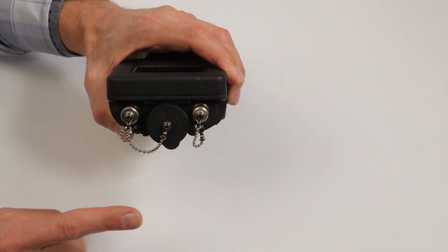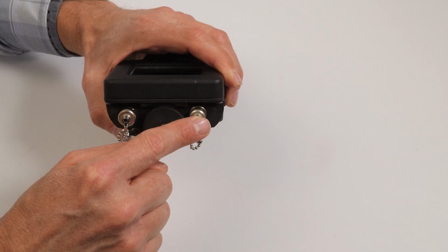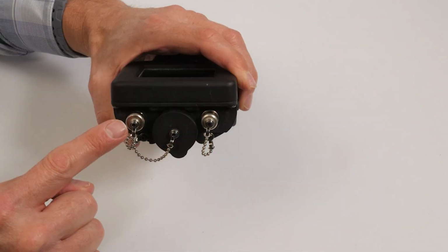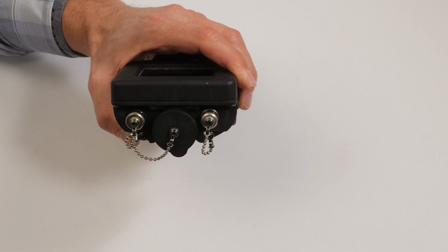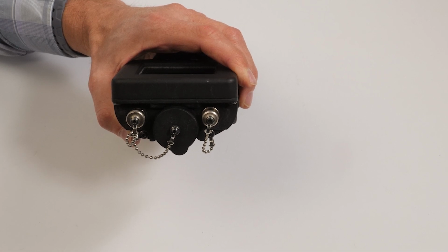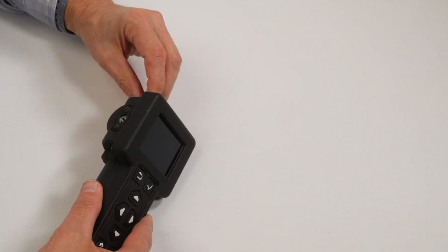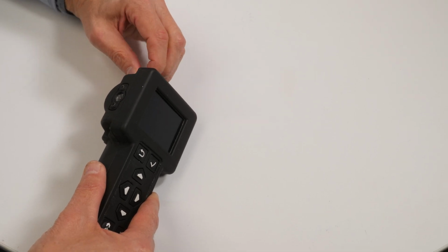The base unit has multiple connectors for interfacing with external devices. On the top, there are 2 connectors. The connector on the left is a 3.5 millimeter audio jack for use with the base unit when using headphones. On the right side, there is a connector for auxiliary power. It can be powered by 110 volts up to 240 volts. The caps covering these connectors are threaded and need to be rotated to remove and install.